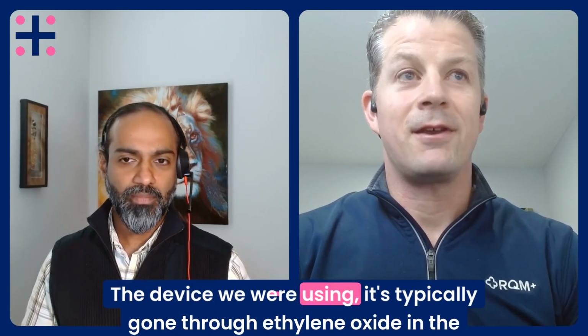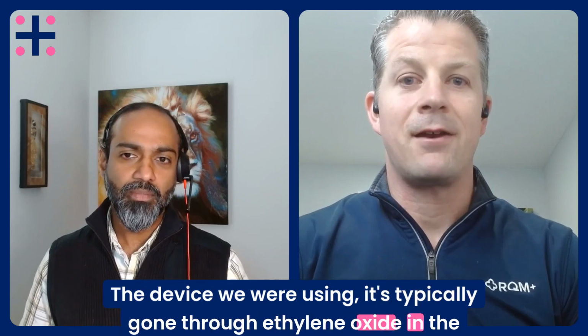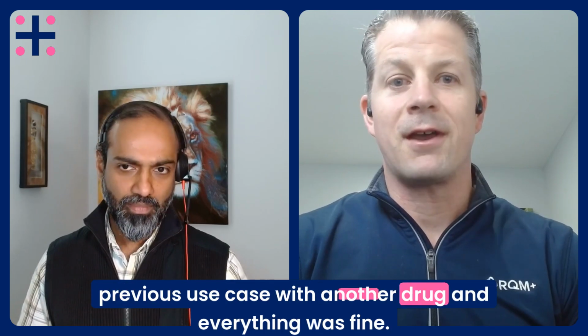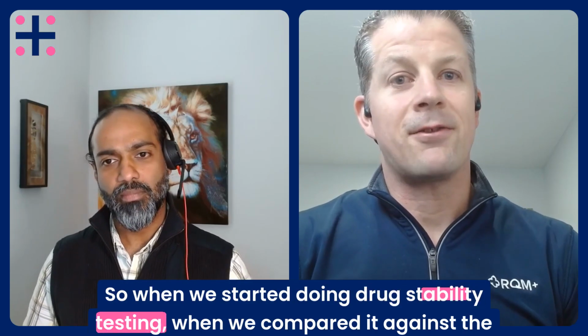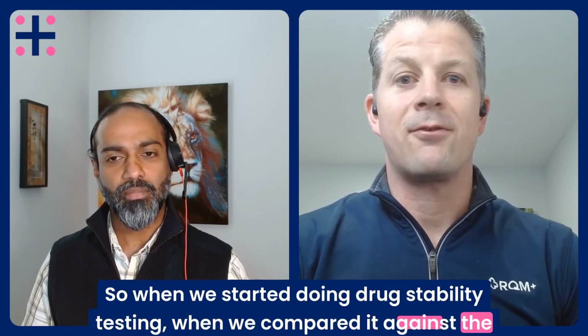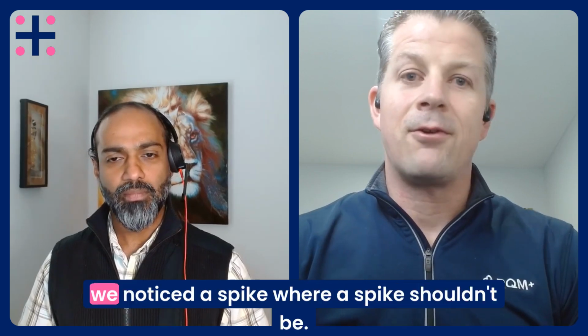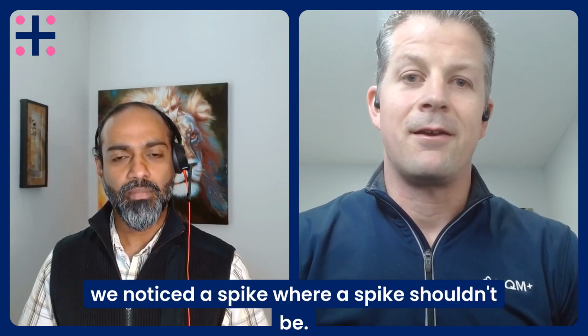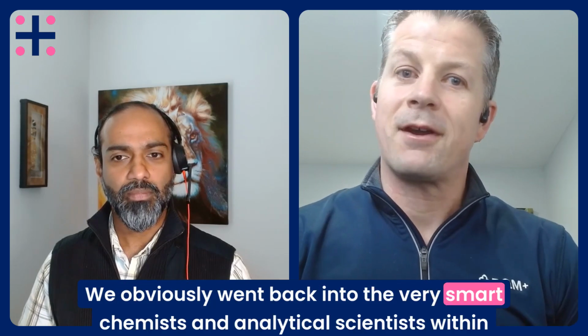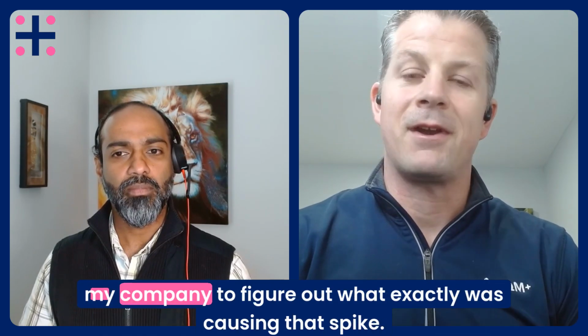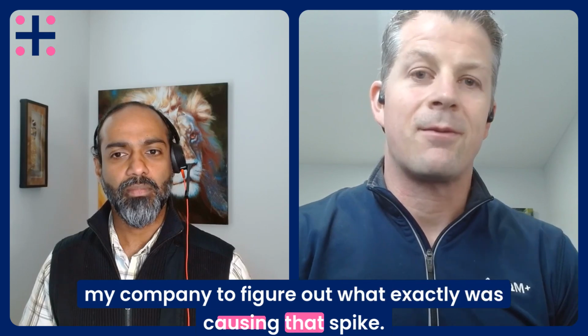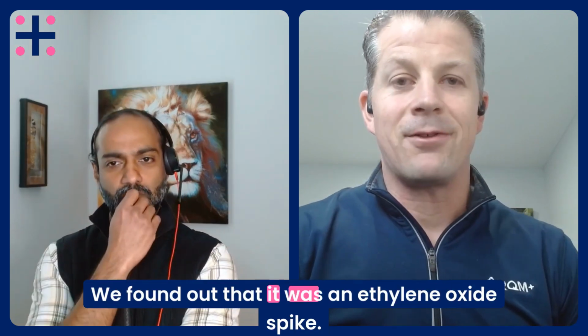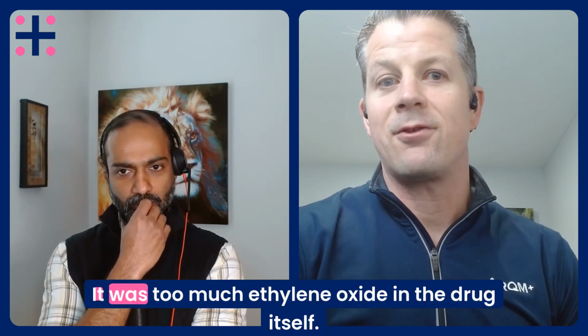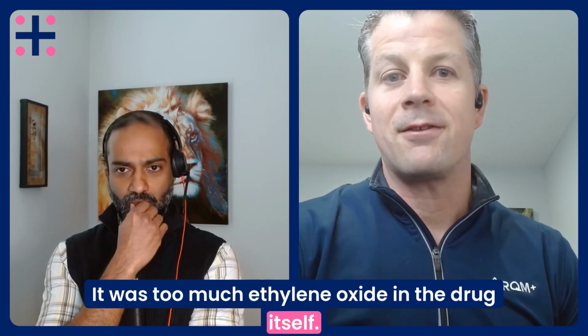And the device we were using, it's typically gone through ethylene oxide in the previous use case with another drug, and everything was fine. So when we started in drug stability testing, when we compared it against the sort of gold standard stability profile, we noticed a spike where a spike shouldn't be. And we had to take it back. We obviously went back into the very smart chemists and analytical scientists within our company to figure out what exactly was causing that spike. We found out that it was an ethylene oxide spike. There was too much ethylene oxide in the drug itself.